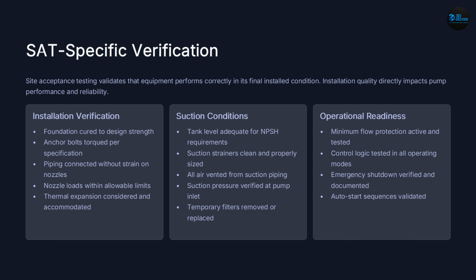The foundation must be cured, anchor bolts properly torqued, piping connected without strain, nozzle loads within allowable limits, thermal expansion properly accommodated. Then comes suction verification: adequate NPSH, clean strainers, air removal, proper inlet pressure. And operational readiness: minimum flow protection, control logic, emergency shutdown systems, auto start sequences. Everything must function together because SAT doesn't test the pump, SAT tests the installation.